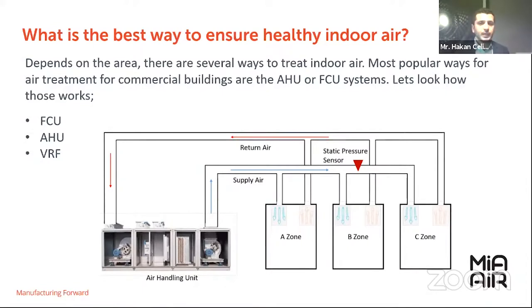In this case, we cannot consider the circulated air to be clean of particles or microorganisms, as these systems are not designed to have HEPA filters, or existing systems don't have HEPA class filters due to fan capacity or cost concerns. So in short, these systems are not the right way to block contagion, mostly during COVID.